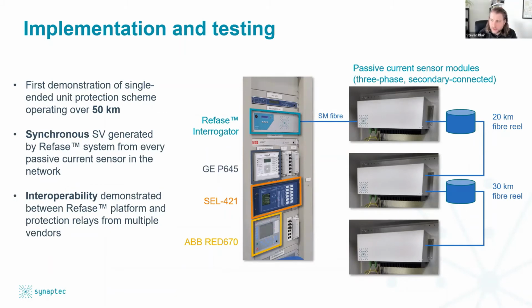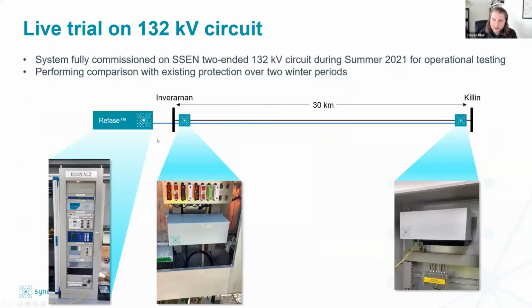For the actual installation, which I'll show in the next slide, we installed this in two substations here in Scotland - it's just a 2-ended scheme for the trial deployment, but they're still 30 kilometers apart, and we're providing the data for differential protection over that long distance, again with no power supply or time sync or any other auxiliary equipment required at these substations, just one IED at one location where it's convenient to have.